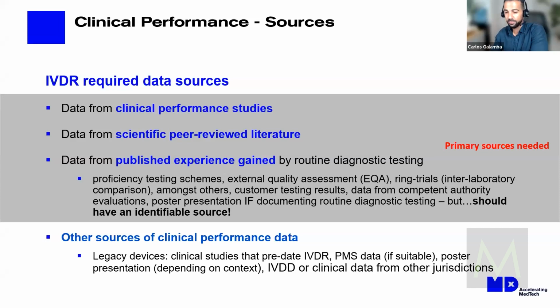Scientific peer-reviewed literature is one of the other sources. This is very common, for instance, with devices that were legacy under the previous IVD directive, and now under the regulation, the manufacturers are demonstrating clinical performance based on articles and peer-reviewed literature that has been published around their devices. And then there's a third potential source, which is data from published experience gained from routine diagnostic testing. That's the one that there's still a lot of debate around: what does published experience gained by routine diagnostic testing mean? But for those of you on the call today familiar with the IVD world, it's understood as being data from, for example, external quality assessment schemes or proficiency testing.